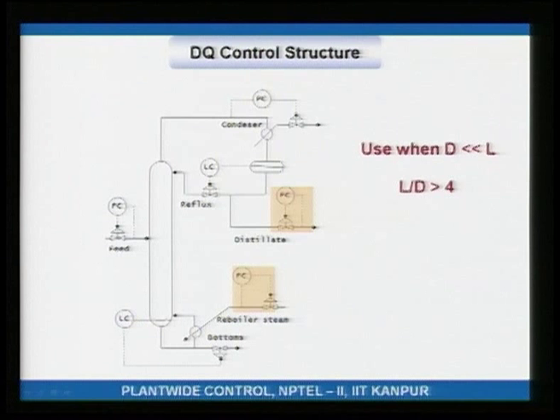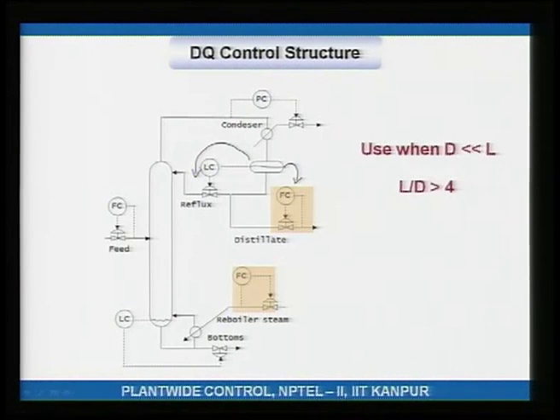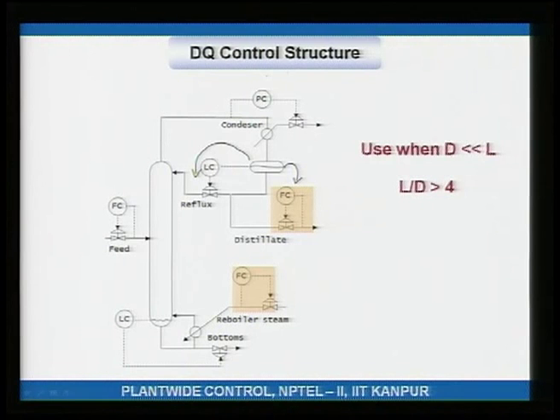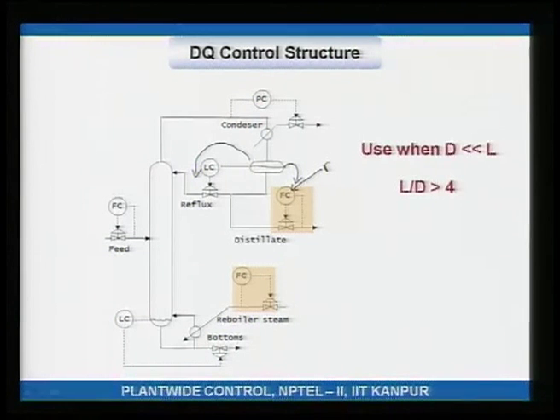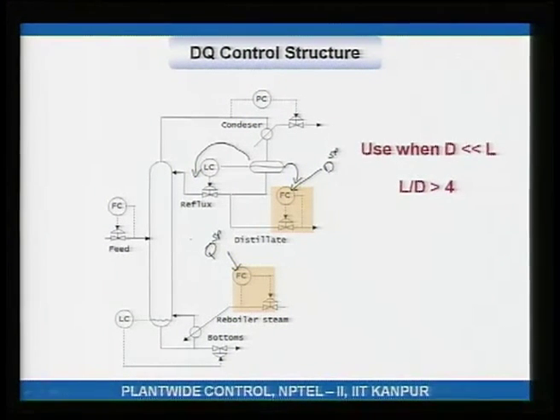In another orientation, the level controller uses reflux to control the reflux drum level instead of distillate. The bottoms level control is as before, and pressure control again uses the cooling water condenser. The two set points left for the operator are D and Q — hence this is called the DQ structure.